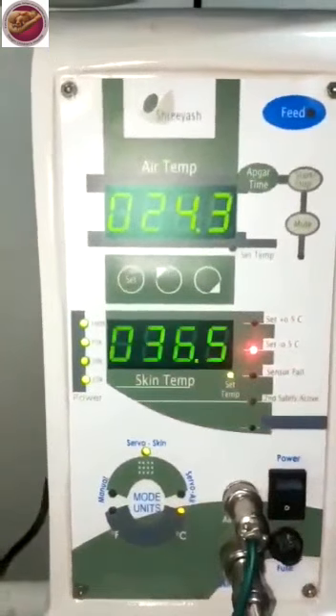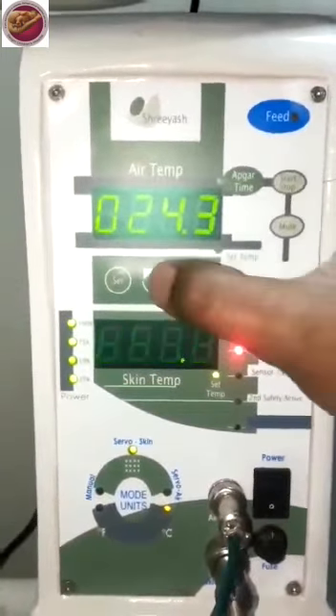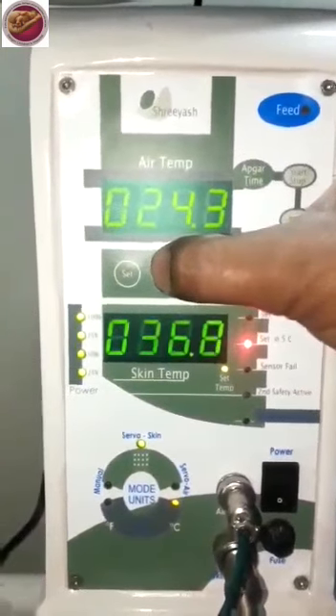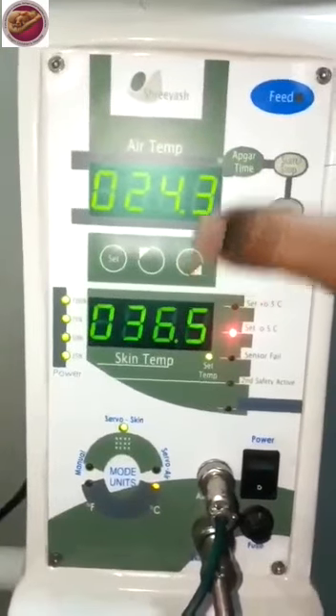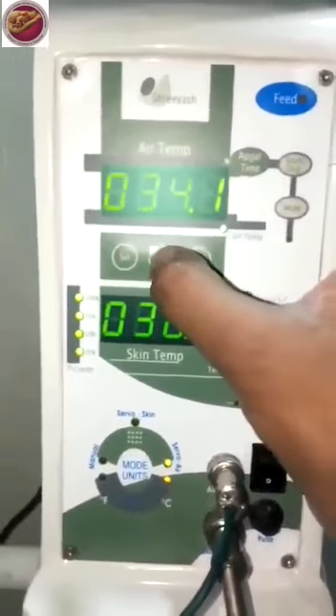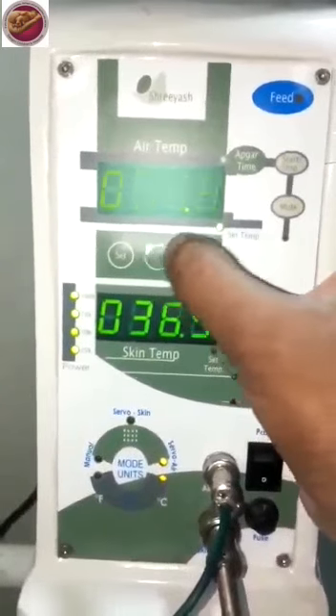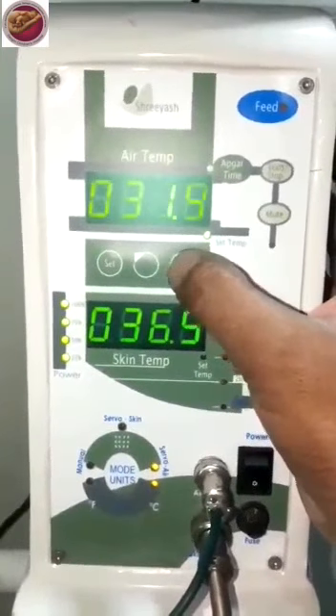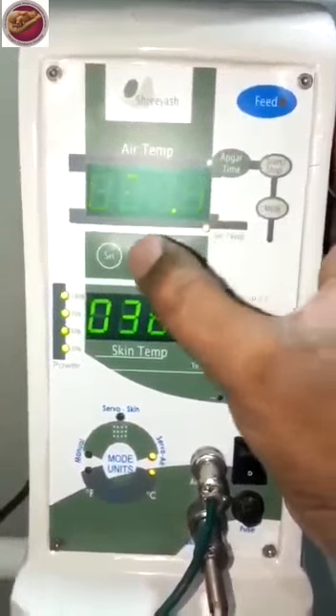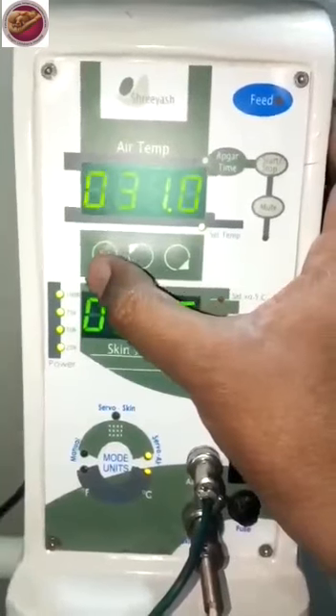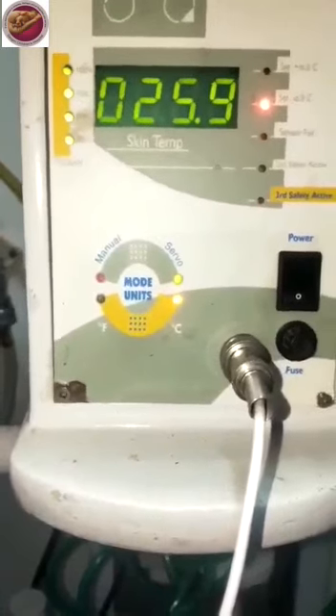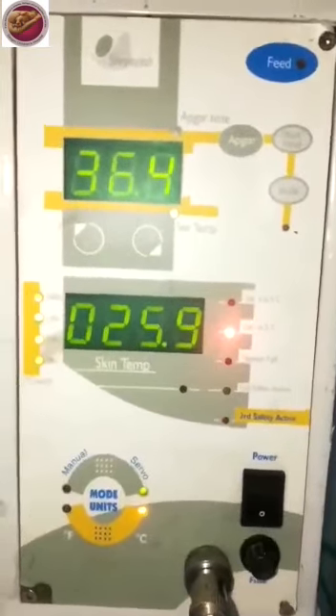In manual mode, the temperature set is default at 37 degrees Celsius for rapid warming. Once temperature reaches 37 degrees Celsius, it switches to servo mode automatically or must be switched to servo mode manually by pressing the button. Control panel has buttons to select the desired mode and probes. It also has up and down buttons to select the temperature setting. Some warmers have only one probe, which is usually used as skin temperature probe.